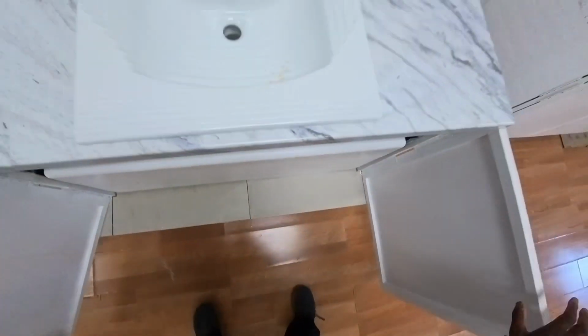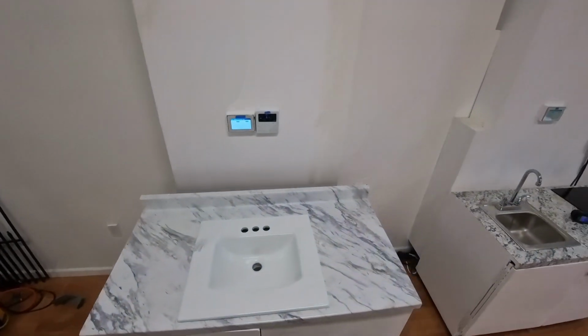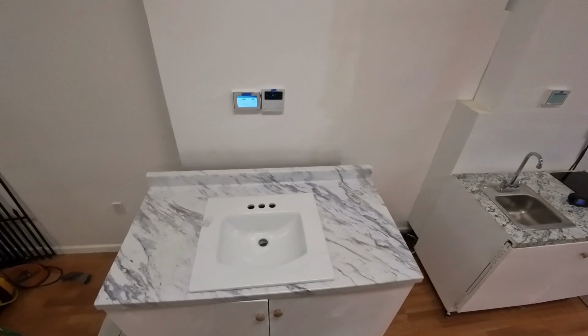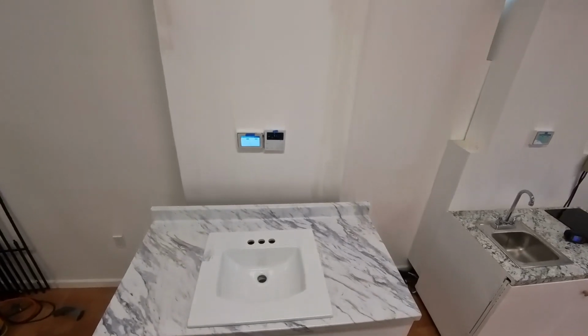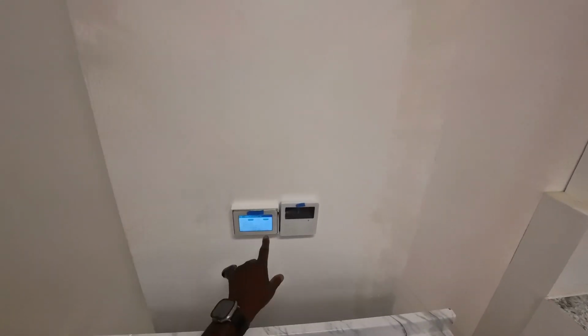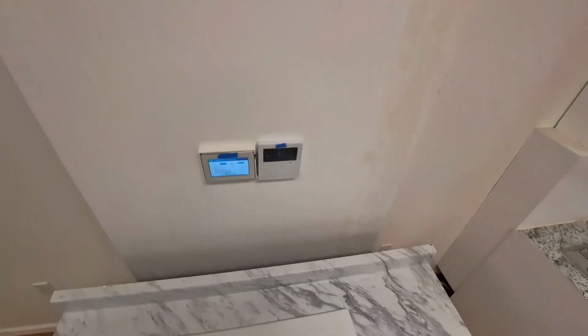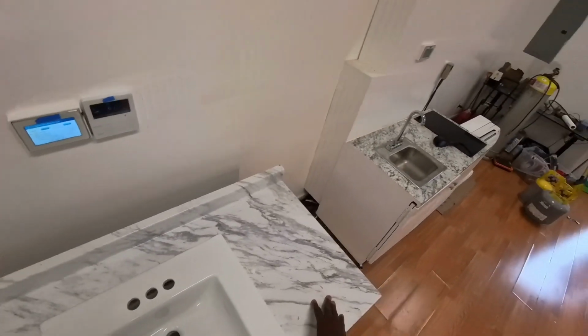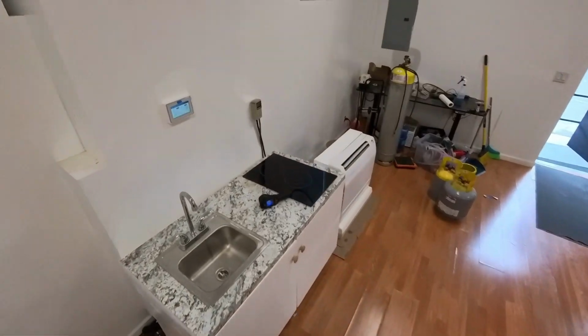And when it comes time to do that maintenance, if you are unable to get an HVAC contractor to come out to take care of your equipment, then you can have a situation like this where if your coil is dirty, you can have a high head pressure situation like that. And if that continues, it can cause your machine to fail.